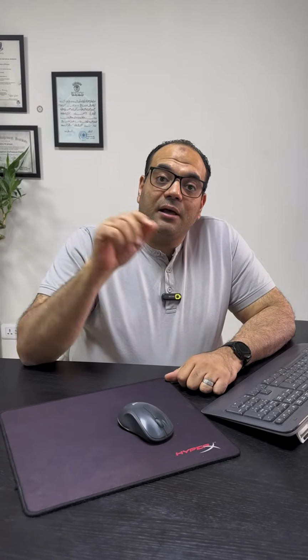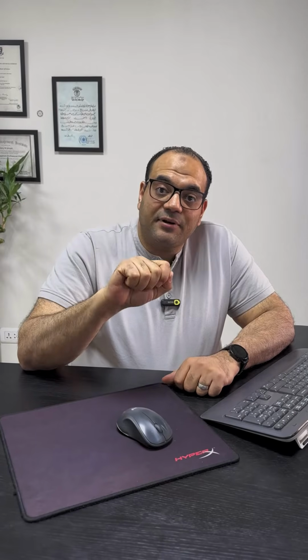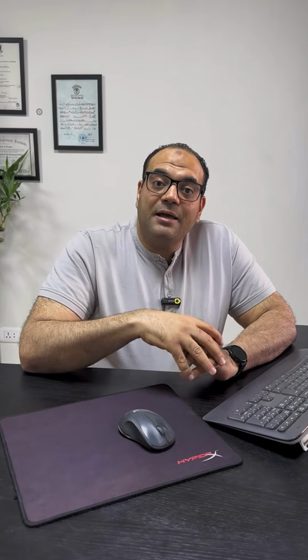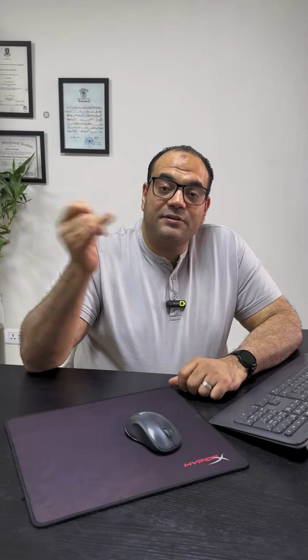So when we do balancing, maybe we will reduce the valve, increase the valve, to be sure that the temperature in the room or in the area meets the required temperature. So we measure the flow of the air and the temperature of the air. This is what we call balancing. And the balancing usually is done at the very end, after we did all the tests for all equipment, for everything, then we start doing the balancing.